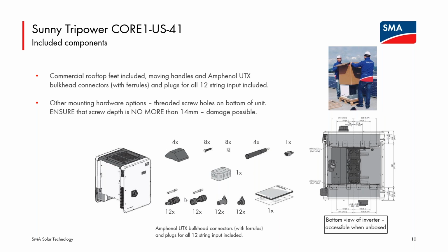And when it comes time to wire up all of the DC, again, we're providing the Amphenol UTX connectors and ferrules to crimp onto the inverter end of the home run wires. So you will be connecting Amphenol UTX to Amphenol UTX here at the inverter body. And sealing caps for the positive and negative connectors that are unused. So each and every positive and negative connector should be receiving something during installation, either being capped or a home run wire being connected to it.